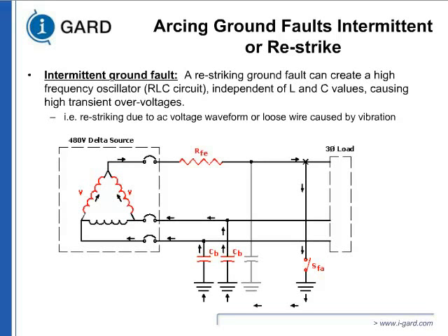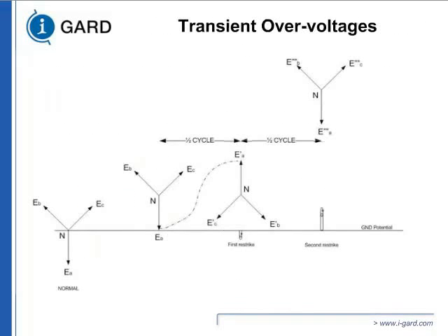How many people who use that Delta ungrounded system have probably had insulation failure on motors as well as on your other circuits? This is what tells you how transient overvoltage rises. On the extreme left, you see a system when it's normal.